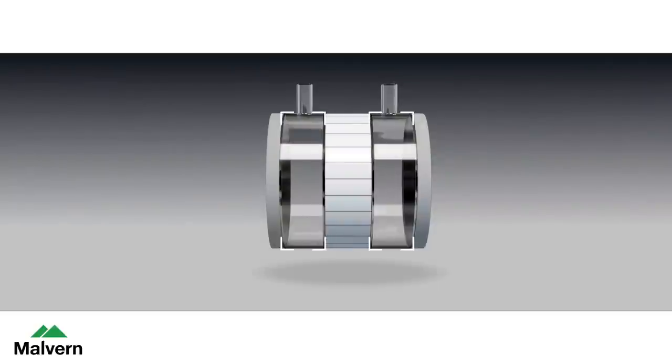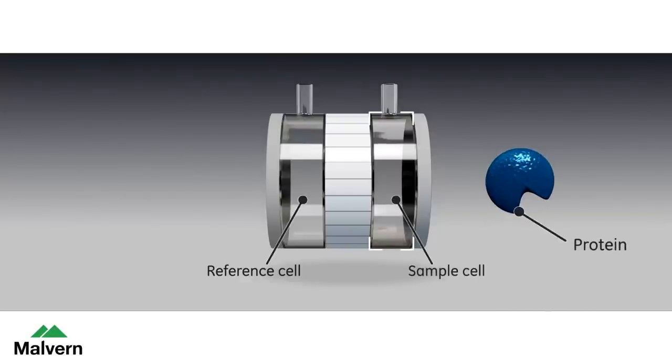In the microcalorimeter there are two cells, one of which contains water and acts as the reference cell, and the other may contain a protein and is called the sample cell. The microcalorimeter needs to keep these two cells at exactly the same temperature.